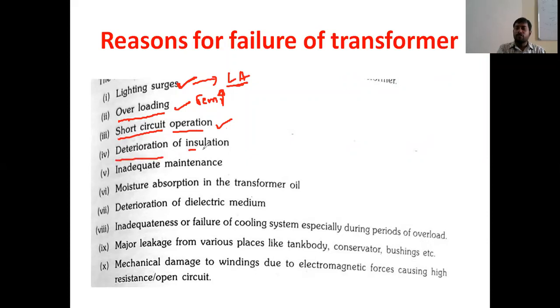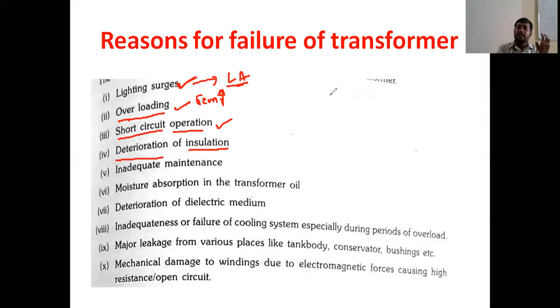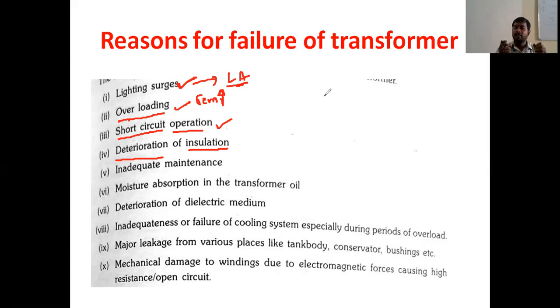Another reason is deterioration of insulation — that is, the aging of the insulation. As the age of the transformer increases, the insulation performance will be poor. The insulation cannot withstand high voltages, and due to the high electric field intensity, the insulation will become a conductor, causing a short-circuit and transformer failure.